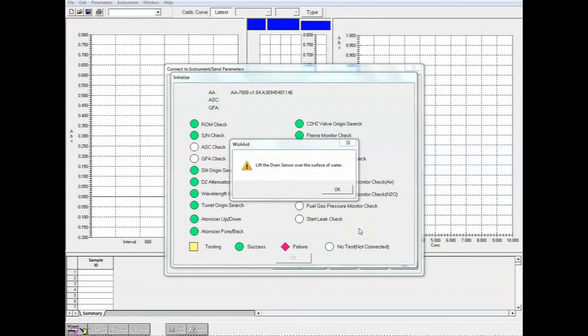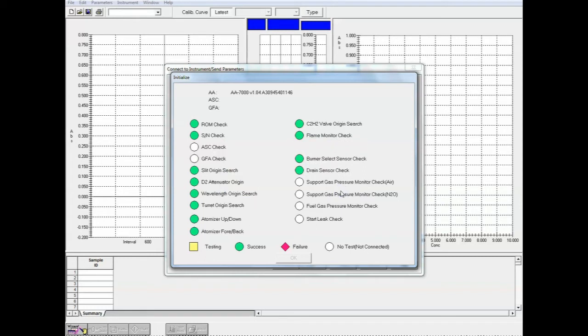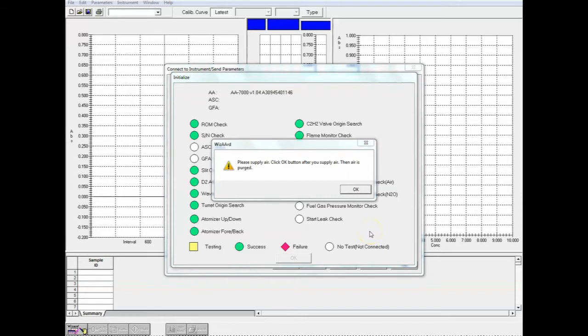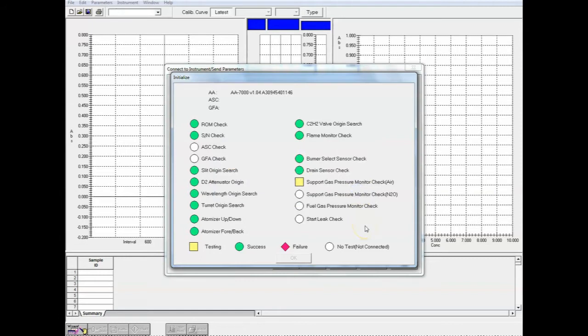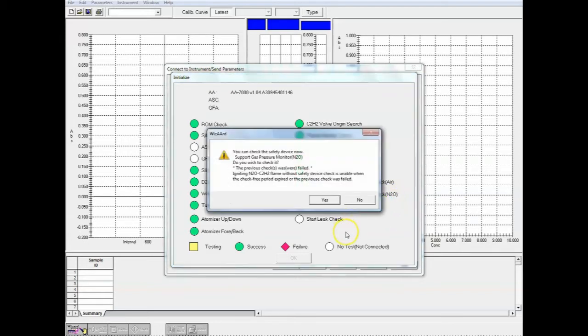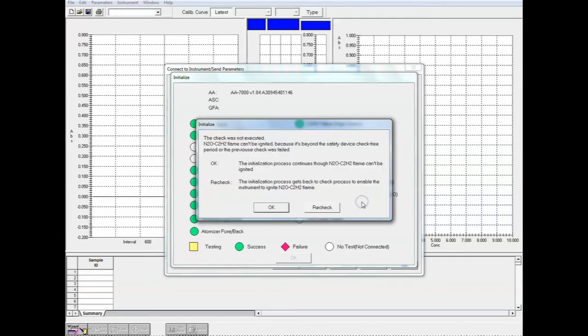So back at our software, here we get the message, lift the drain sensor over the surface of the water. So I do that, I hit OK, and now it wants us to move the drain sensor below the surface of the water. And say OK. Please supply air. So it's clicking the OK button after we supply air, so make sure the air is on. It is, so we hit OK. You notice again there's the N2O check, which we are not using. So we'll say no, we don't wish to check it.